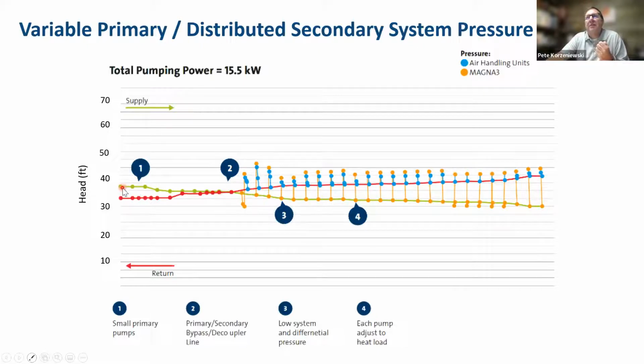The second difference that you'll see here is as we generate the head from the hot side of the system through the chiller to pick up that chilled water energy and start traveling out to the system, you're going to see a crossover here at the bridge or at the decoupler bypass, whatever terminology you use. Essentially in this system, we're going to take a route of low pressure. So we're going to travel out to the system, out into our zones at a continuing lower pressure than where we started. And that's where the distributed pump is going to pick up its job.